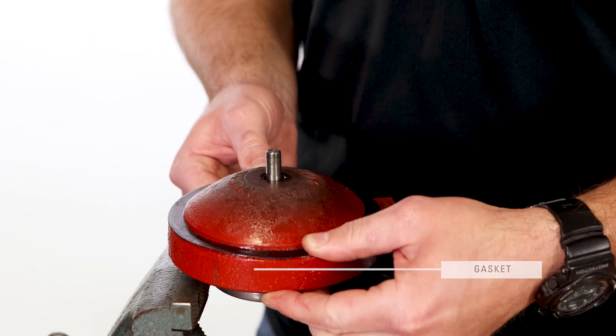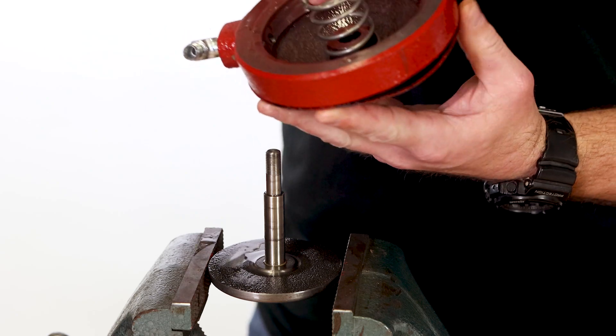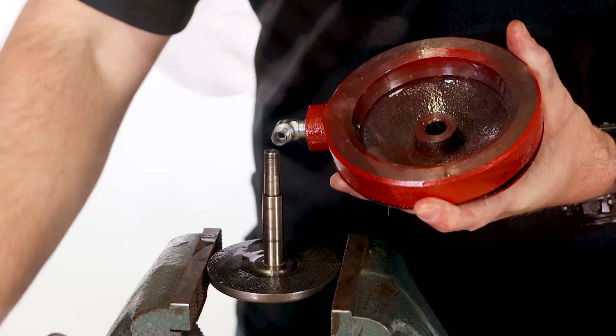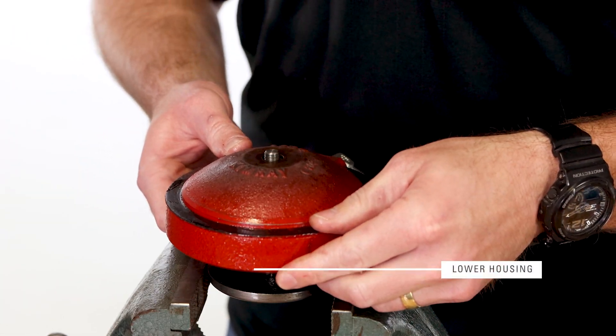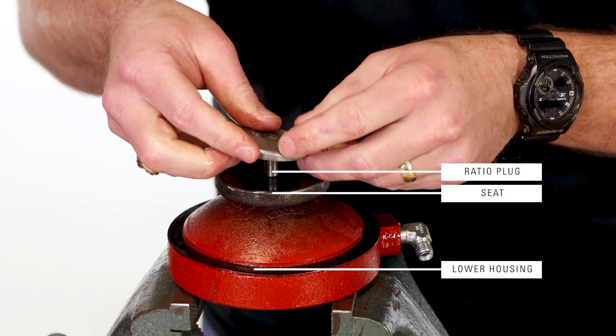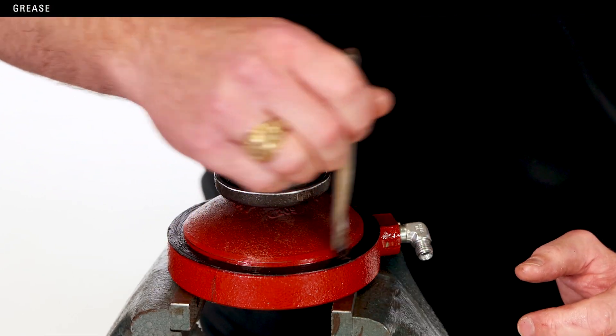Check the gasket for damage and then remove the lower housing. Remove the spring and set it aside — this will be an extra part for this conversion. Reassemble the lower housing, seat, ratio plug, and nut. Apply new grease to the gasket.